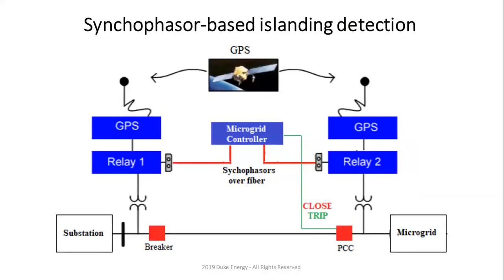Essentially what happens is that on the source side of the breaker, you have a relay that has GPS. You have communications to the microgrid controller. On the load side of the PCC, you have a relay with GPS also connected to the microgrid controller. And now the microgrid controller has to use synchrophasor data to detect the islanding. Why? Because as the breaker opens, the voltage starts deviating, the frequency starts deviating, the rate of change of frequency starts deviating. So from that standpoint, you can see that there is a way to detect it, right?